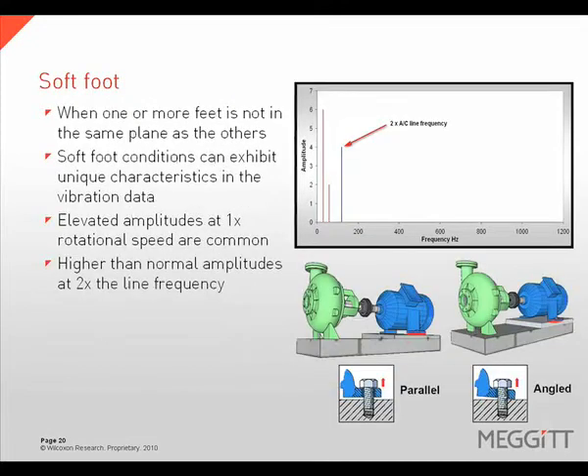Soft foot is a condition that occurs when one or more of the machine feet are not in the same plane as the others. Soft foot will create an elevated 1 times rotational speed vibration and a higher than normal amplitude at 2 times line frequency if it is on a motor. This elevation in 2 times line frequency is created when the soft foot is tightened and the foot pulls on the case, creating case distortion.